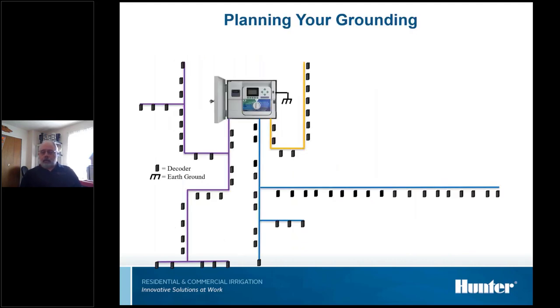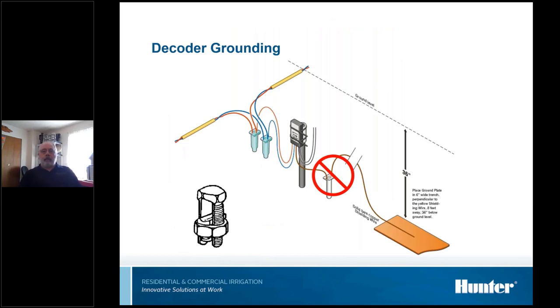I have one more question coming in, Dave, too. I think it deals with the resistance of grounding, and Greg asks, can you just talk for a second about checking the ground with a megger and the use of GEM ground enhancement material? Just what kind of readings they're looking for, possibly? So basically, and I've got a slide with GEM on it later, we're hoping to get a resistance reading of 10 ohms or less, which is measured with what we call a megger. It's a special meter that basically induces a voltage into the ground and measures how well that whole setup conducts electricity.